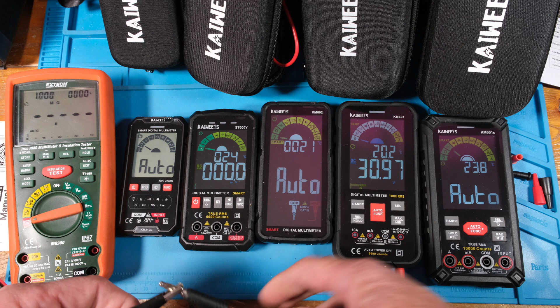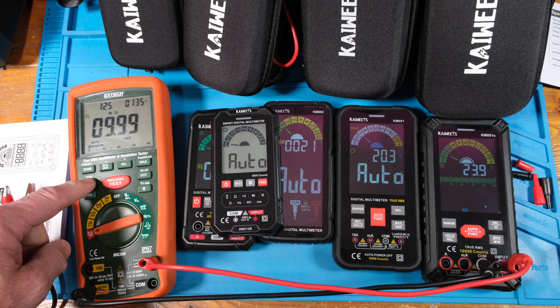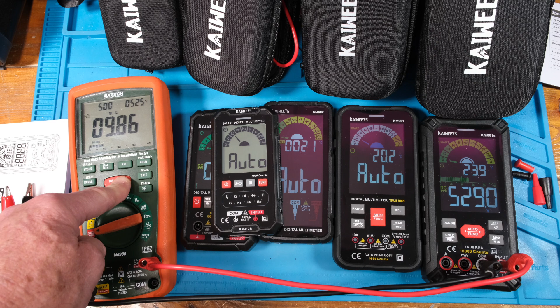Okay, beeping overload, 9.8 over there. Here, I'll go to 500 just to show that it can read the 500. There's 125, let's do that. Okay, it's saying 135, and we got 135 here. There's 250, let's go to 500. There's 500. And we're at 529, that's saying 525 over here on the Extech.